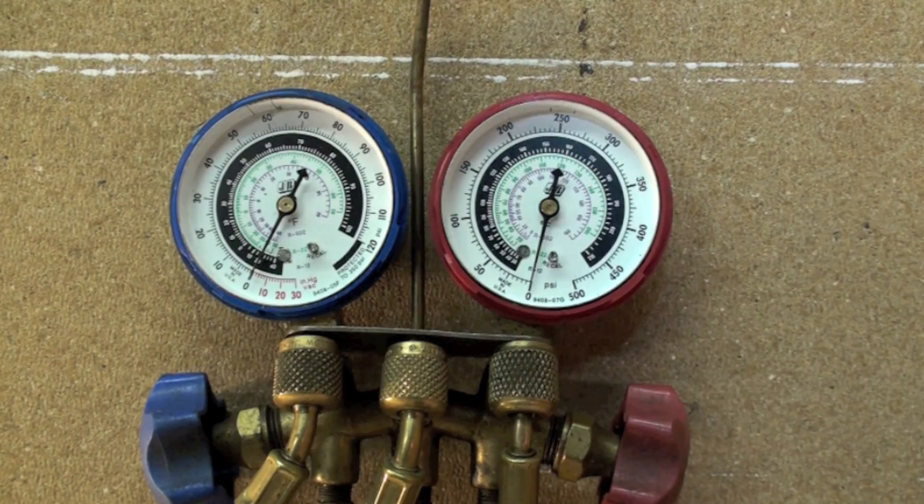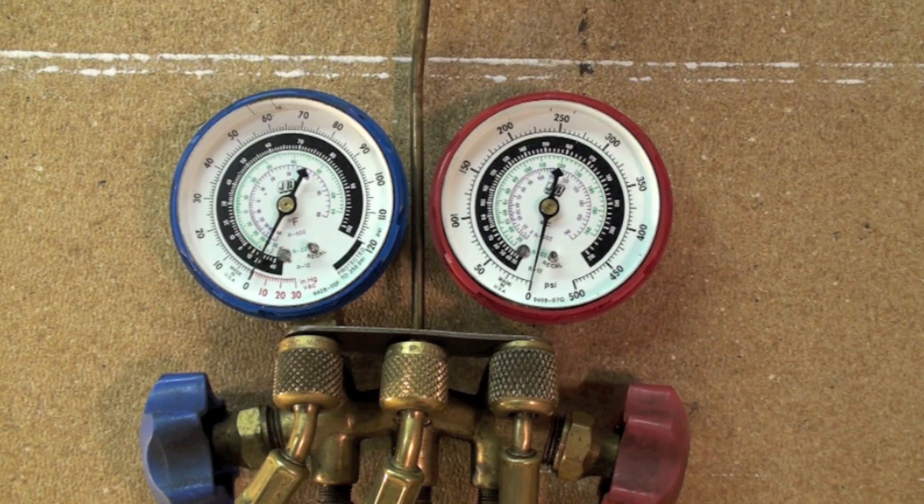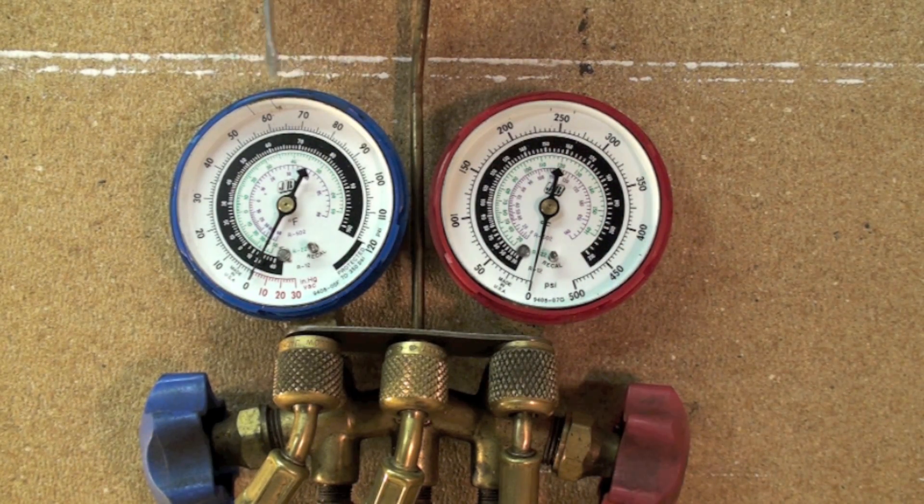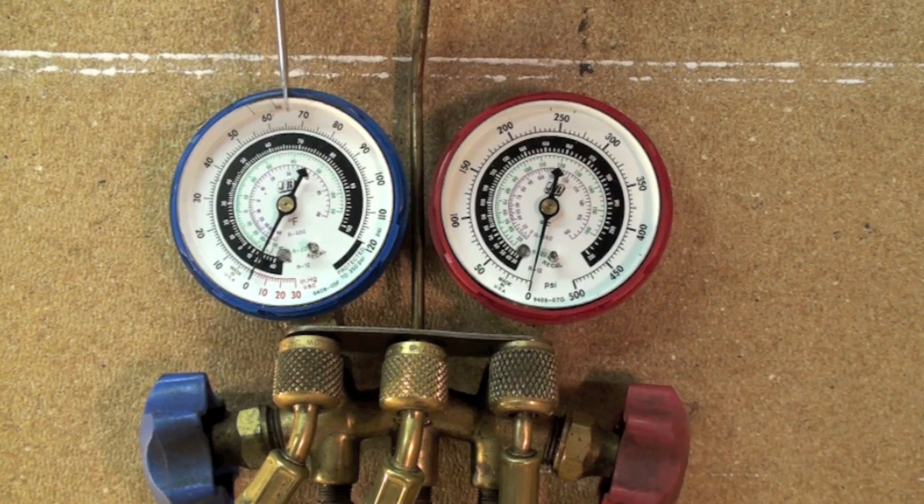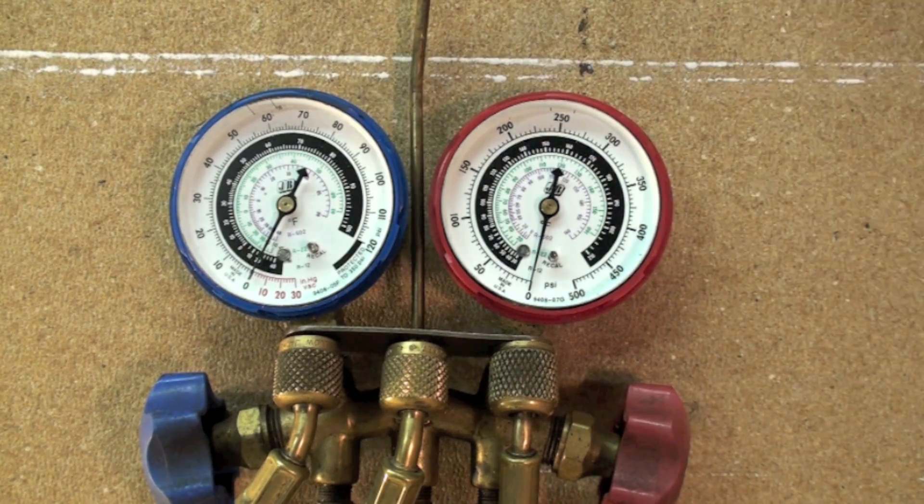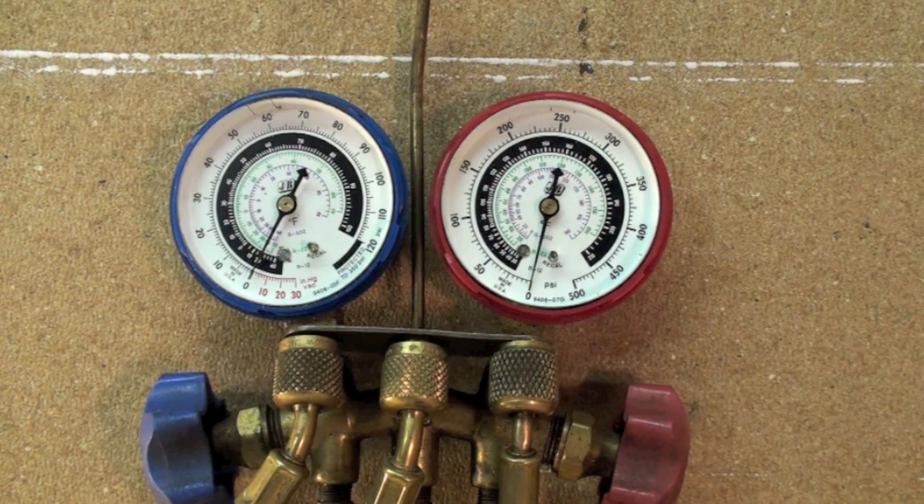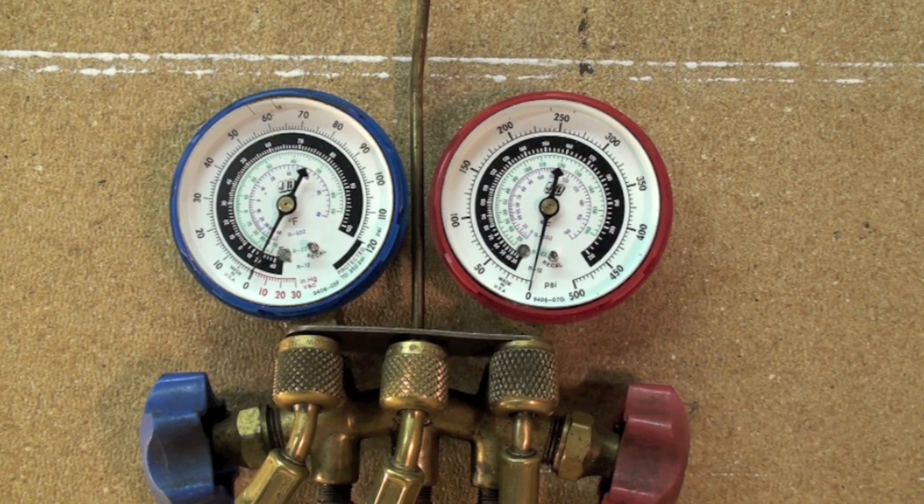But if you're over four or five pounds off on this thing, that can make quite a bit of difference in the evaporating temperature here and of course condensing temperature there. Not quite so picky on the condensing temperature because a gauge isn't going to show it that close anyway.